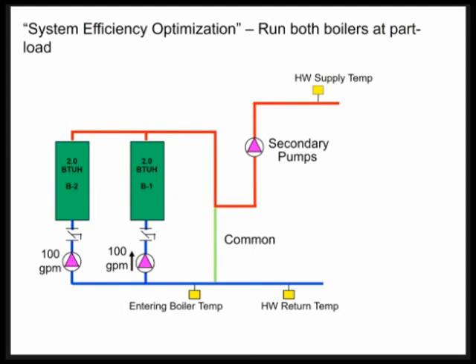So I've decided to turn on the second boiler and let them both run at 50%. But because we are constant flow in the primary, I'm running two pumps. I now have 200 GPM in the primary loop. Two 100 GPM pumps supplying 140 degree water to the common pipe and to the secondary zone. Remember, I haven't changed the load on the secondary. I'm still 2 million BTUs. So my flow rate hasn't changed in the secondary. I have 100 GPM going out to my building, and now I have 100 GPM going across the common pipe because we're not using it in the secondary. And this is how primary or secondary works. It's perfectly okay, perfectly normal.